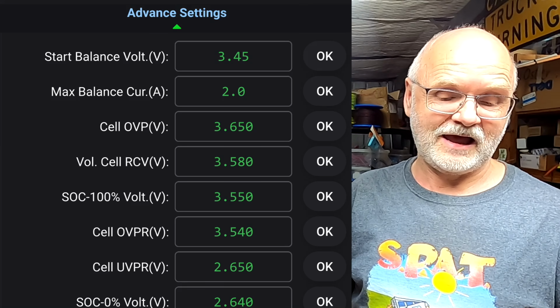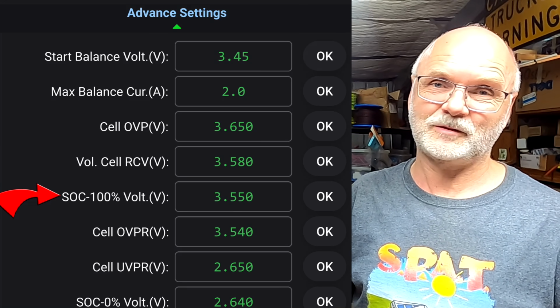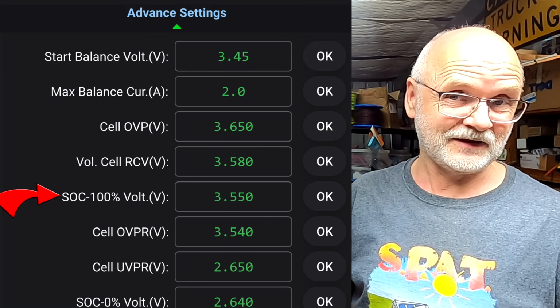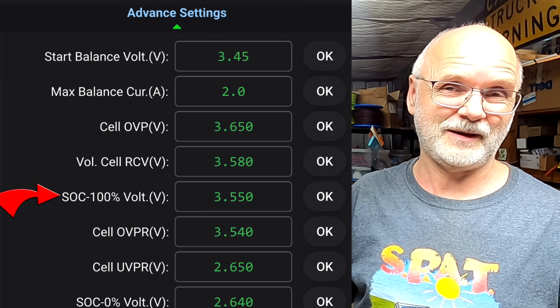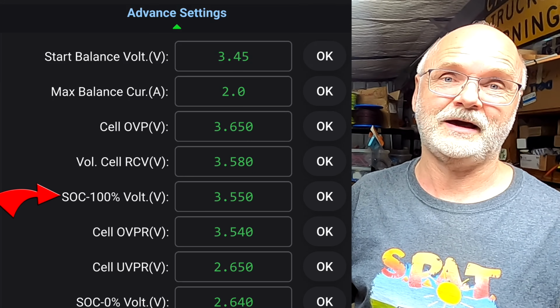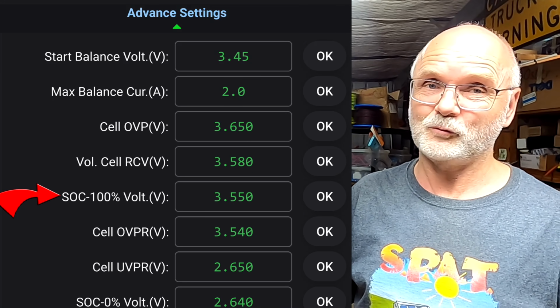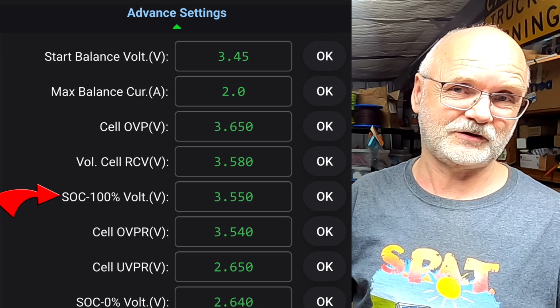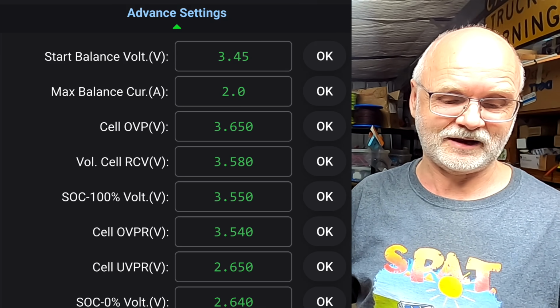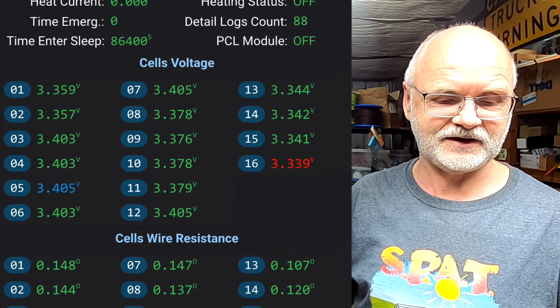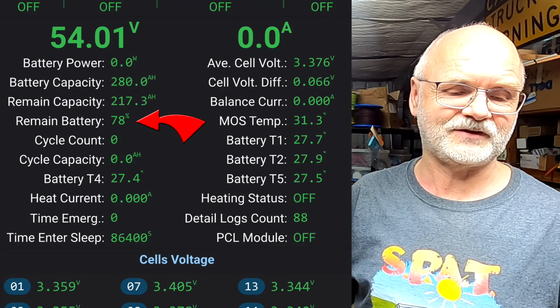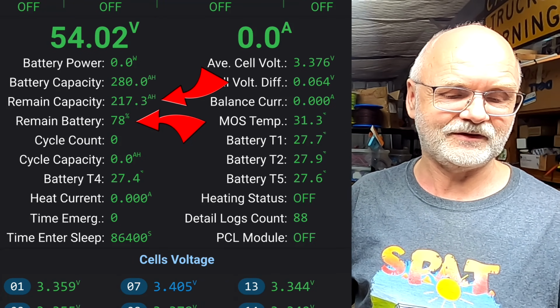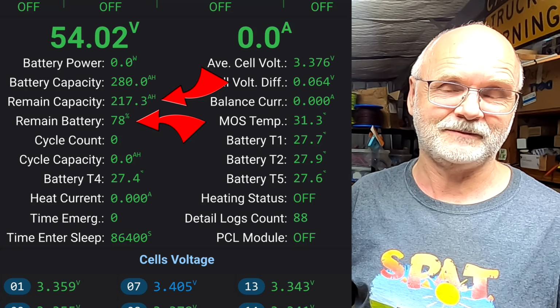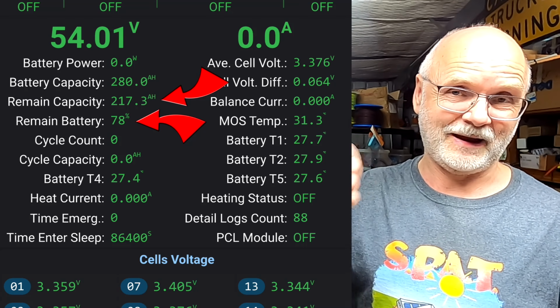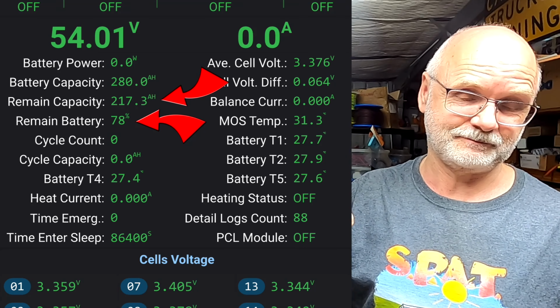Right below that we have a state of charge 100% voltage. This is a value where your BMS resets to 100% state of charge. So if one cell reaches this voltage, it resets to 100% state of charge. You can see it up here. It also sets the remaining capacity the same as the battery capacity, so it resets both capacity and state of charge.